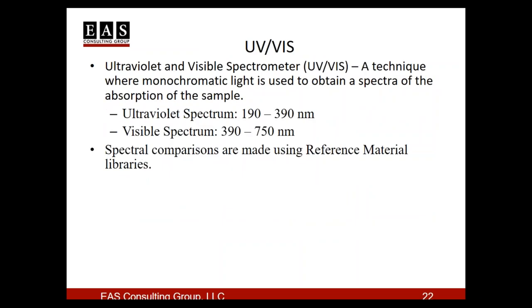We're going to go through a few different types of equipment you will typically see in an analytical laboratory. One of those is UV-Vis, a technique where monochromatic light is used to obtain a spectra of the absorption of the sample. UV is between 190 and 390 nanometers, and visible spectrum is 390 to 750. You take a scan and get the spectra of your sample, then compare it to a reference library of a known standard that's already been characterized.